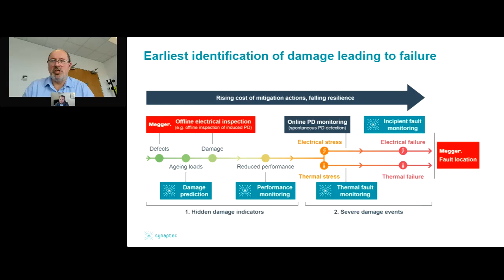So I just wanted to quickly address how this works in comparison with partial discharge monitoring, because that has likely popped into the minds of people in the audience. So we try to categorize things here and show where Greenlight fits in. So there's offline testing, which can include partial discharge monitoring and other things like Tan Delta to inspect the insulation quality effectively. So that, of course, has value. It's a very useful diagnostic tool, but it obviously requires the cable to be out of service so that signals can be injected at the appropriate levels, at the appropriate frequency to excite these events and see what happens. There is also a category of monitoring for partial discharge, which is done online.